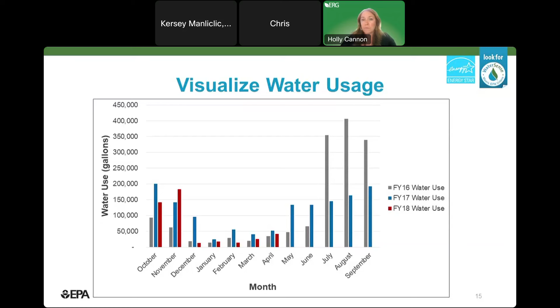If you have multiple years of data, it's very helpful to include all of it so you can see trends year over year. If you see outlier data, like a spike in the summer of 2016, you want to interview facility staff to get to the bottom of what happened. It could have been a leak that was resolved, a water efficiency project implemented in the cooling tower that reduced use in 2017 and 2018, or it may just be that the summer of 2016 was particularly hotter and drier with more cooling use.